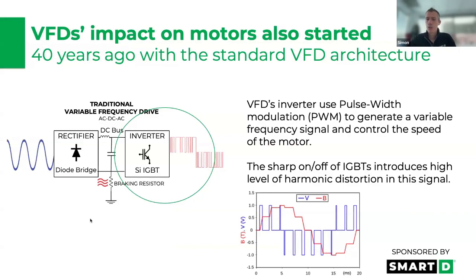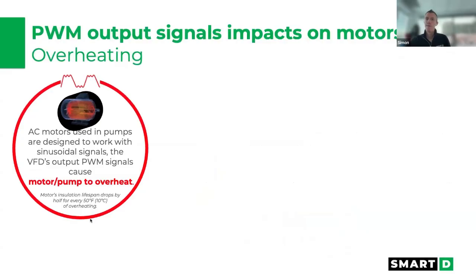Again, I'm not going to spend too much time because I assume everyone is already quite knowledgeable about this topic, but pulse width modulation is the way you create this variable frequency signal in current. So you're doing these high-speed pulses, typically between 2 and 8 kilohertz, switching in an IGBT-based drive. With these high switching pulses, depending on the duration of each pulse, you're able to recreate a pseudo sine signal in current. However, because of these high-speed pulses, you are generating harmonics, and we've seen it in the other graphs. It's a much more messy distribution of harmonics.